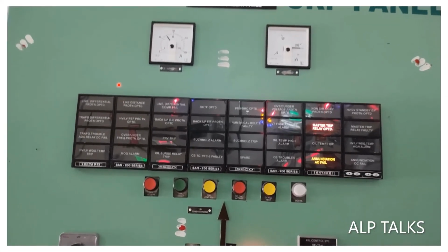These are the different annunciators we have, for different signaling purposes. This is for the power transformer. We have line differential protection, transformer differential protection, transformer trouble, auxiliary relay DC fail, HV LV winding temperature trip, line distance protection, HV LV reference protection. We have over or under frequency protection, MOG alarm, line differential common failure, backup over current protection, PRV trip, oil surge relay trips, backup earth fault protection, Buchholz relay, CB, numerical relay fault, spare contacts, oil temperature indicator, non-directional. Yeah, we have so many different things here. Oil temperature trip.